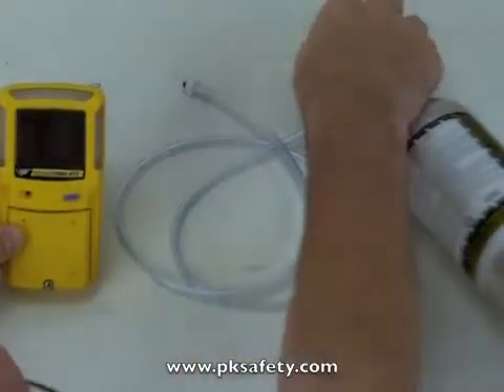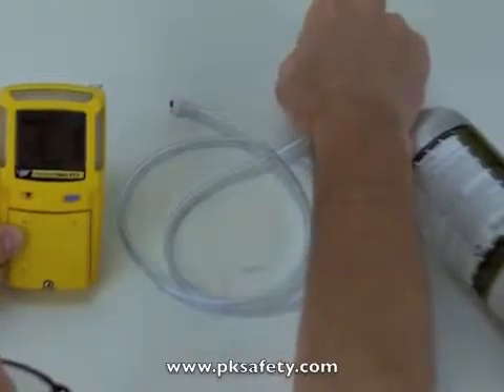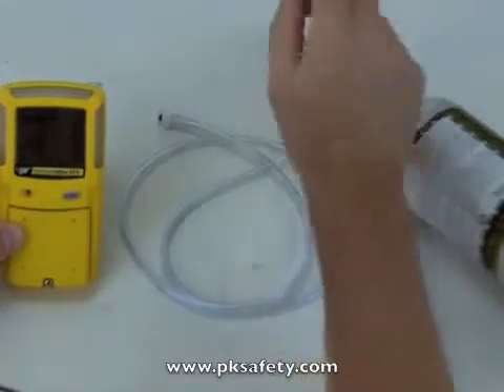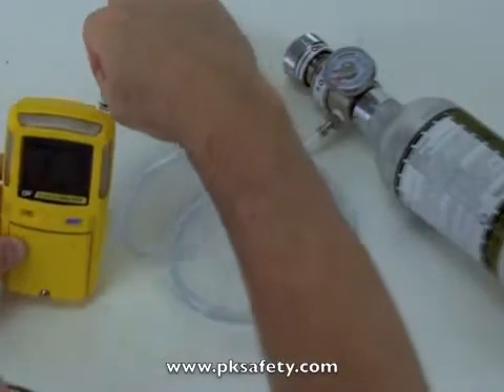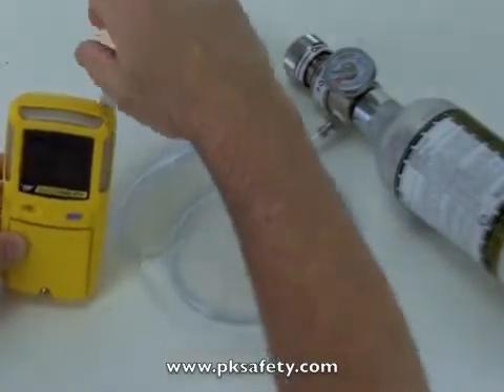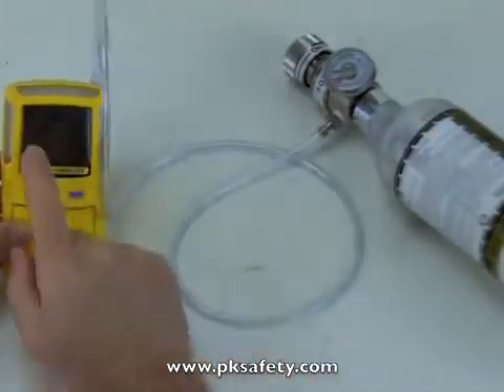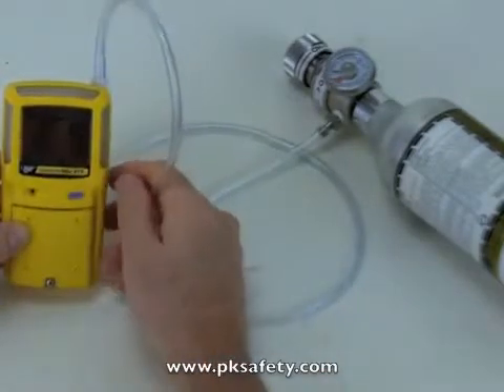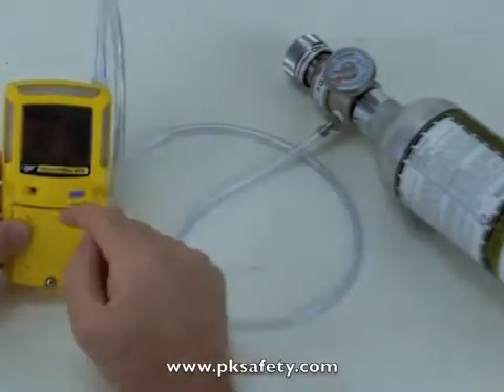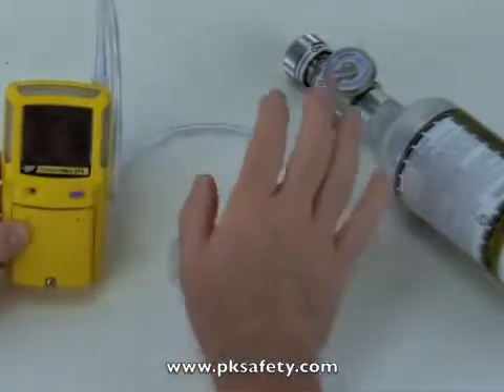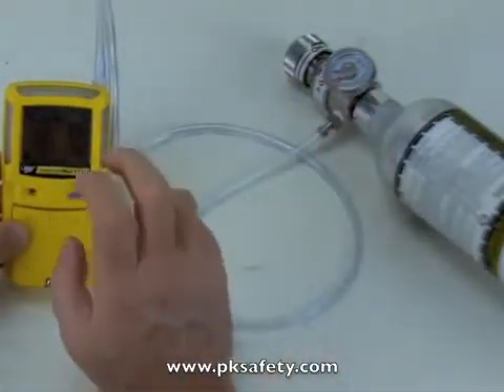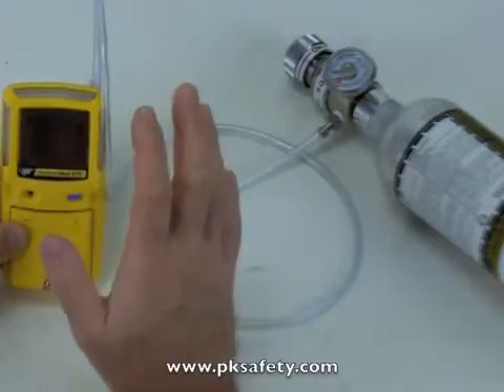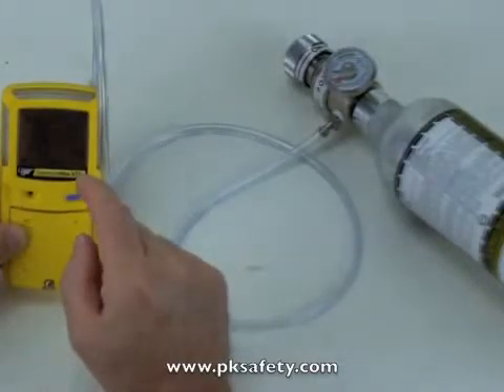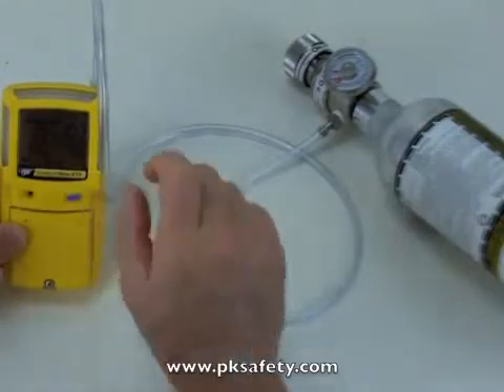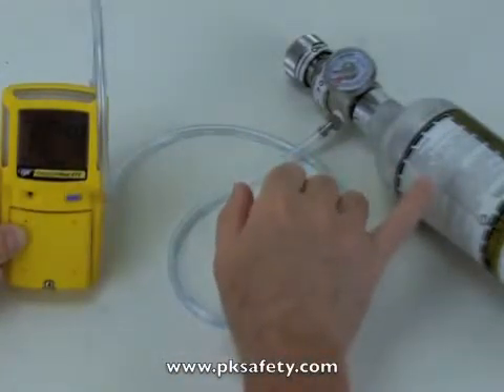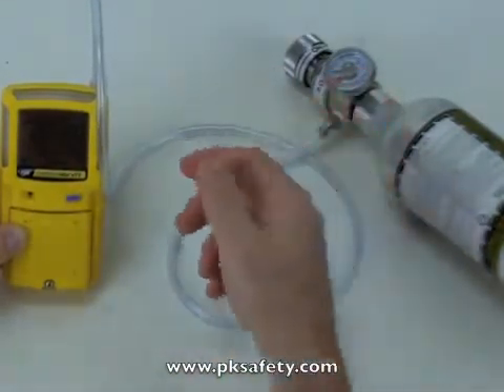So first thing I'm going to do is turn on the cylinder of gas. The gas is now flowing. I take this hose and I attach it with the quick connector, and immediately the reading starts to rise. And this is in response to the gas, and it's going to come to very close to what's listed in this cylinder. After a period of time, which is approximately a minute, the unit's going to self-adjust to the exact specifications that are on this cylinder. And this is a cylinder they intend for you to use.